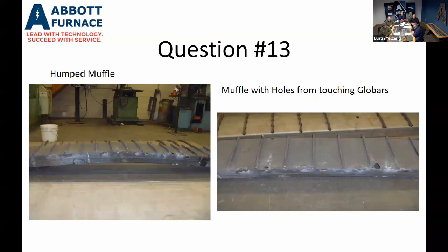So we have a procedure written up that we'd feel free to share if anybody's interested. So we put our new muffle in, our furnace is cold. We're going to bring that furnace up to 400 degrees. We always ramp at 100 degrees an hour Fahrenheit. And that, as Donnie talked about, the Globars, the electrical components, everything, that's going to give us a nice even heat rate. We're not working things too hard to bring it up at that speed. So we're going to bring it up 100 degrees an hour. We're going to get to 400. We're going to stop for 2 hours. And then we're going to do our next step.